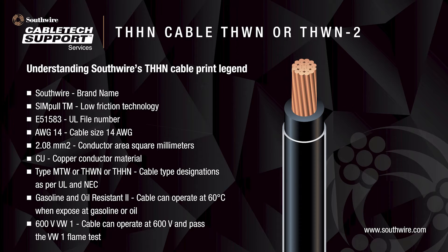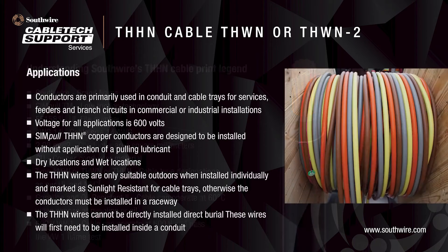Every Southwire THHN cable has a print legend. It will include the manufacturer's name and brand — for example, Southwire SIMpull — and compliance information like the UL file number. The conductor size, area, and material are also listed. In this example, a 14 AWG 2.08 square millimeter copper conductor. The print will also have the cable type designation per UL and NEC, such as MTW, THWN, or THHN. Other optional ratings such as gasoline and oil resistant or sunlight resistant will also be listed. Finally, the maximum operating voltage, which in this case is 600 volt.